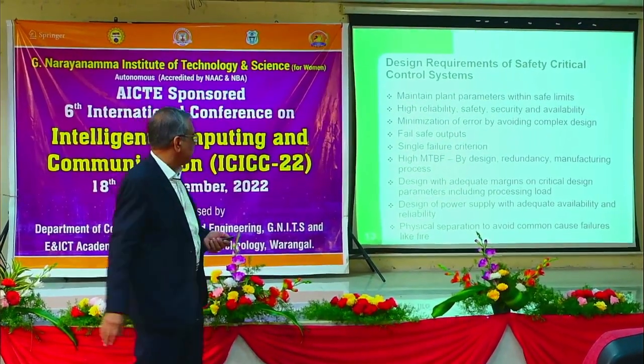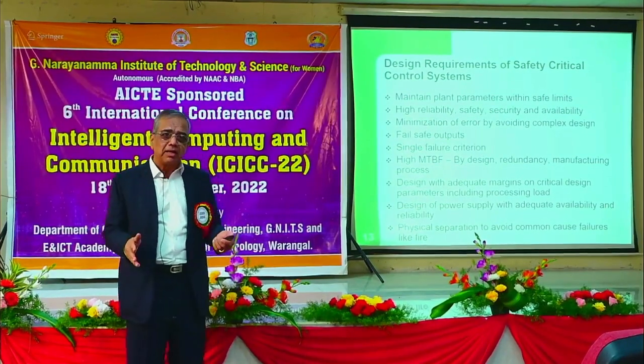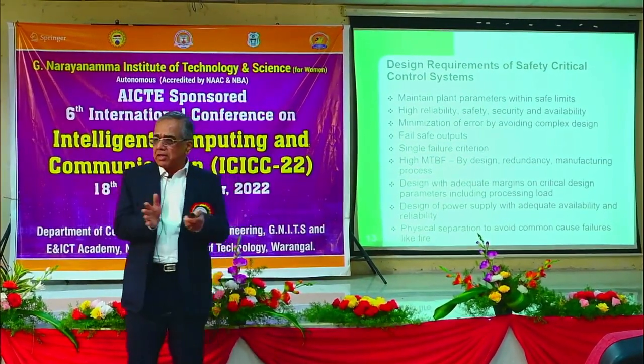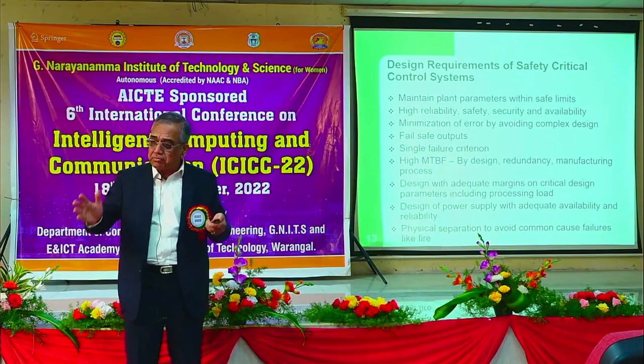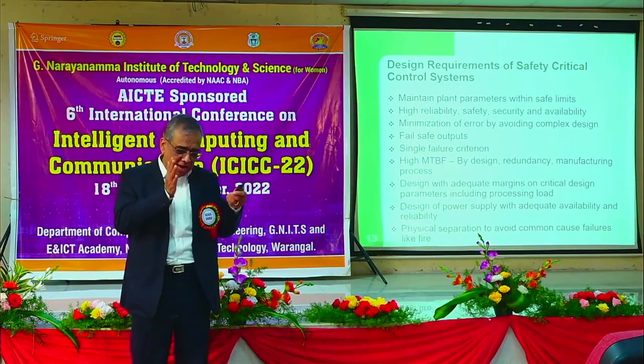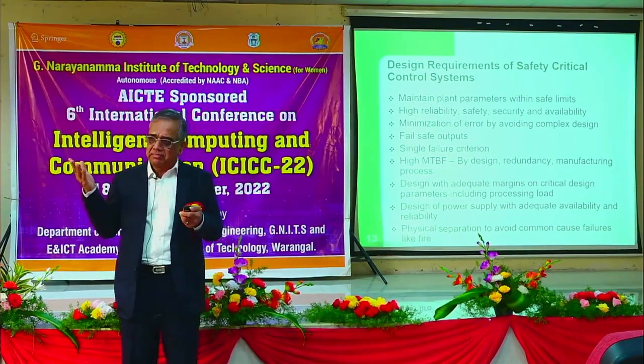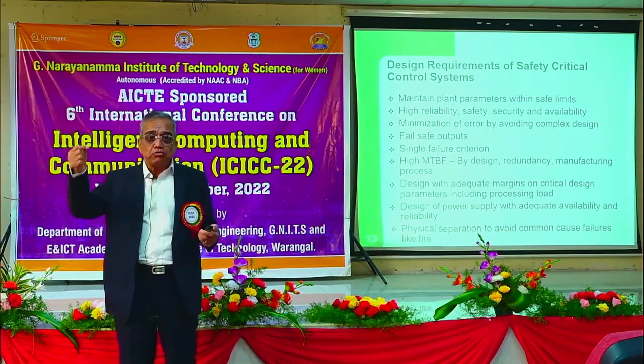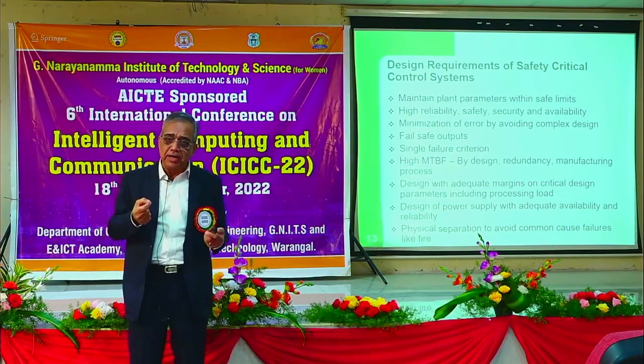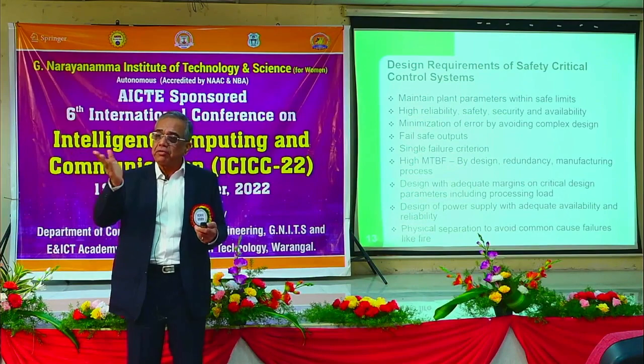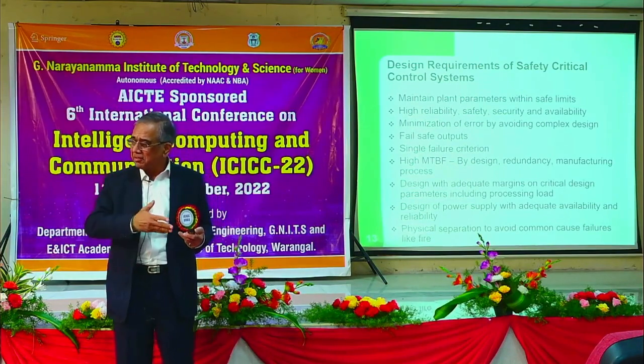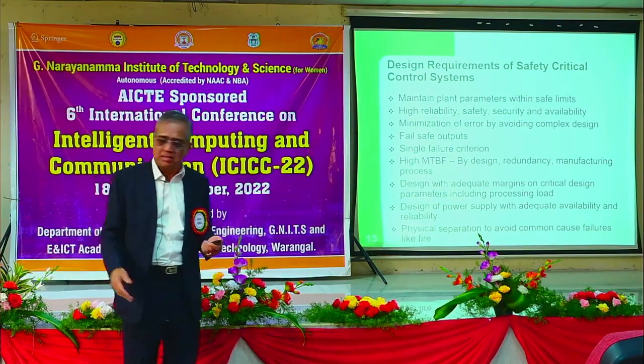Physical separation to avoid common cause failure. Again, the 3 control systems are not kept together, they are kept in different rooms with fire barrier. So the fire in one room does not affect the other system. Also those cables which are coming from the field, from the sensors, are routed through different routes, so that fire in one route does not affect the second system.